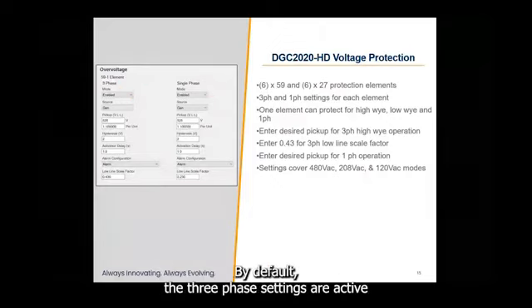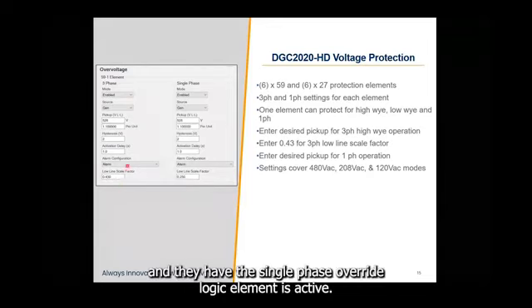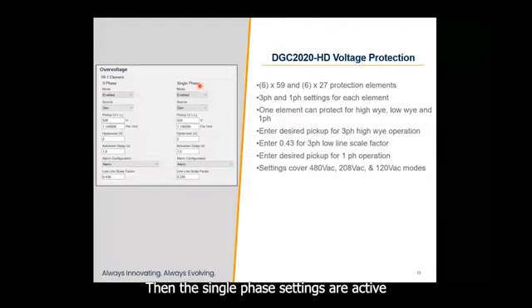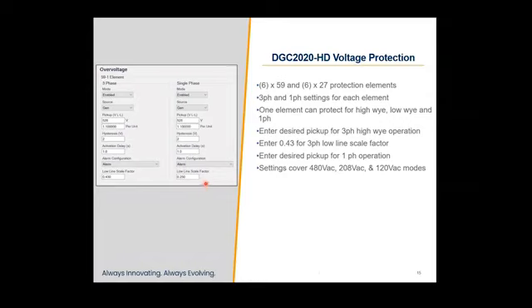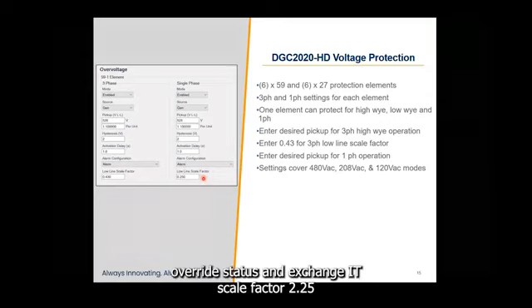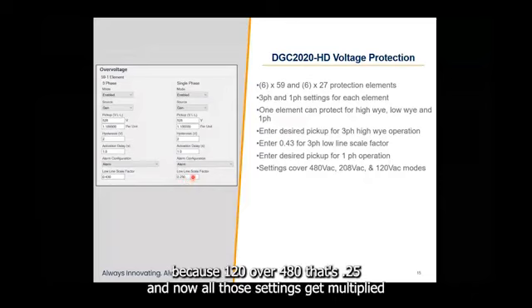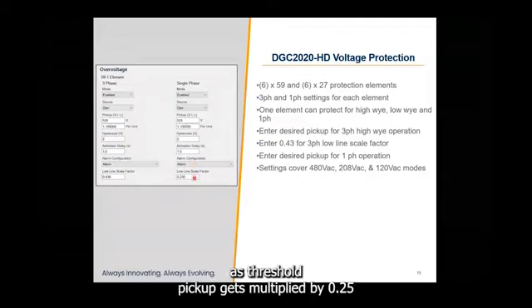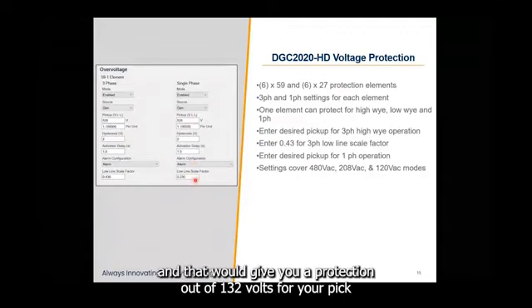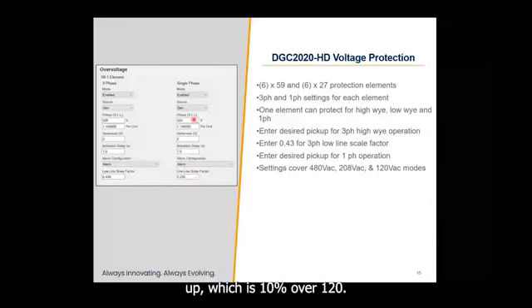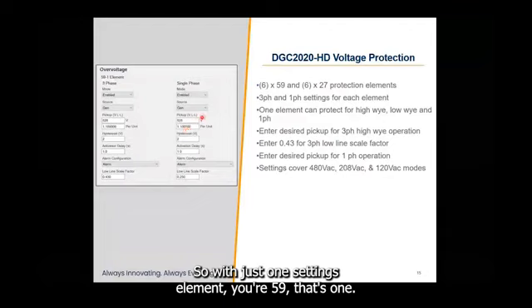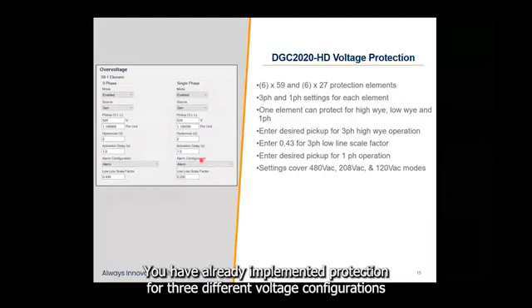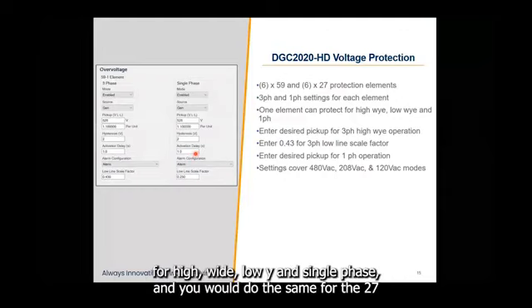By default, the 3-phase settings are active, and if the single phase override logic element is active, then the single phase settings are active. And you also would give the controller a low line override status, and change the scale factor to 0.25, because 120 over 480, that's 0.25. And now all the settings get multiplied. This threshold pickup gets multiplied by 0.25, and that would give you protection at 132 volts for your pickup, which is 10% over 120. So with just one settings element, your 59-1, you have already implemented protection for 3 different voltage configurations, for high Y, low Y, and single phase.